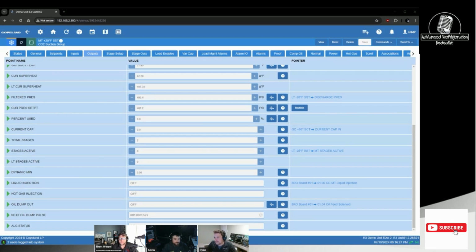Yep, exactly. I'll play around with PSS. I'm sure I'll give you a superheat value for the 4M SLS. So the SLS is the low temp, and the 4M TLS is the medium temp transcritical compressors. I'm sold on just having recips on the low temp. I don't like the scrolls on the low temp. The recips just seem way more robust.